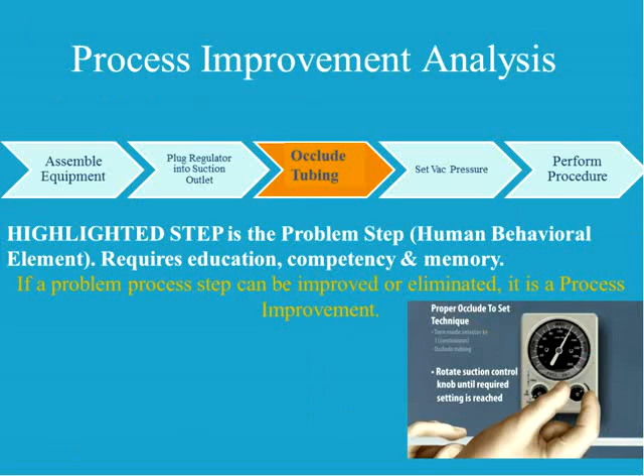And so with new technology, there's an ability to assemble the equipment, plug the regulator into the suction outlet, and what's called push to set the vacuum regulator. When you actually push the regulator knob in to set the pressure, it actually occludes the vacuum system for you.